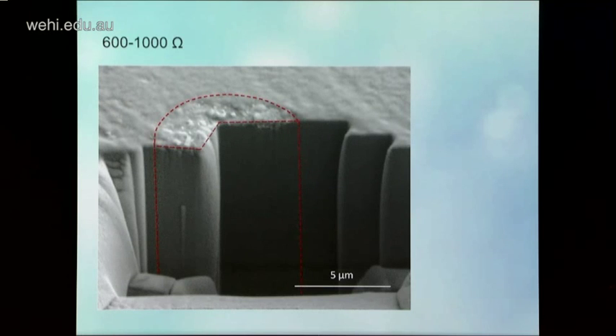This is an SEM image that's been cut through with a focused ion beam. So we are just looking here. The red lines indicate where the conducting diamond is, as opposed to the insulating diamond, which is over here. We've never seen a gap in this diamond, which is why I think they're just so reliable. They're really very, very, very hermetic.